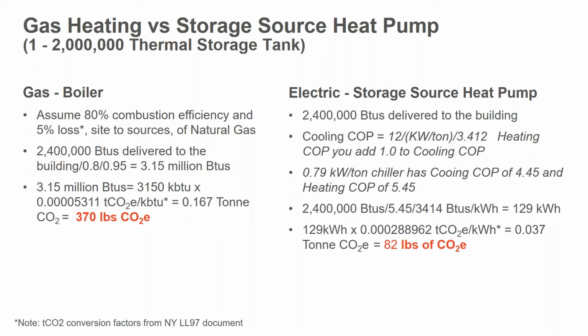So when you're talking cooling COP, what you have to remember is when you change it to heating COP, you add 1 to it. And that makes sense. Let's say you have, in the example here, a chiller that has a 0.79 kW per ton. That is equivalent to a cooling COP of 4.45. Well, because you are adding the electricity, you're putting 1 unit of electricity in, you're moving 4.45 with the heat pump process, and now you have to reject 5.45. So it's a very high heating COP with a centrifugal chiller making ice.